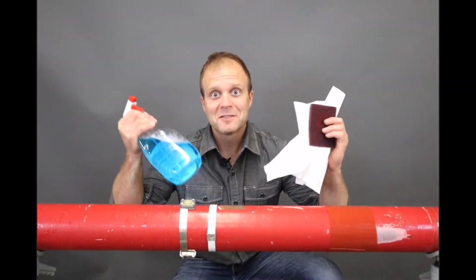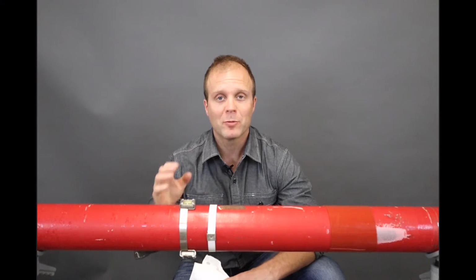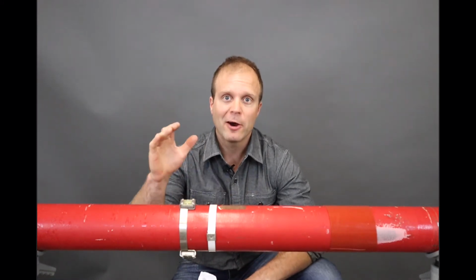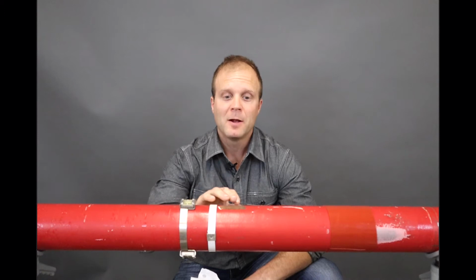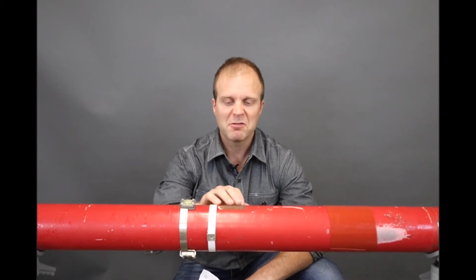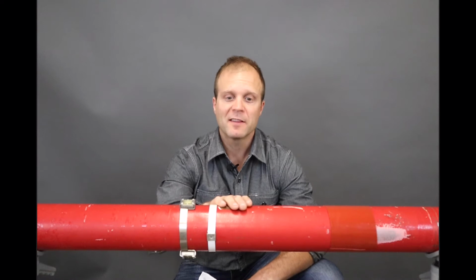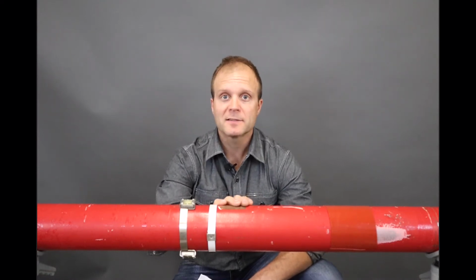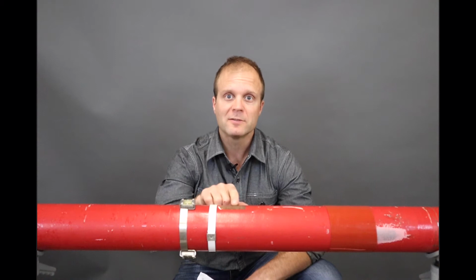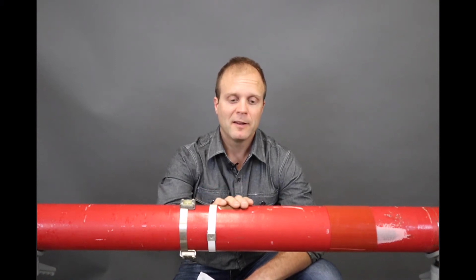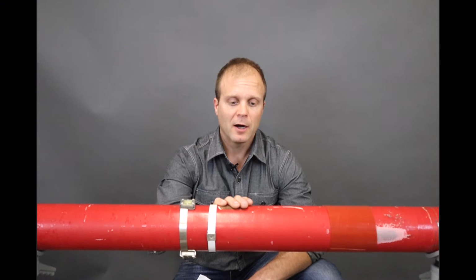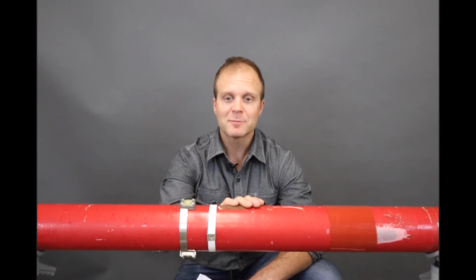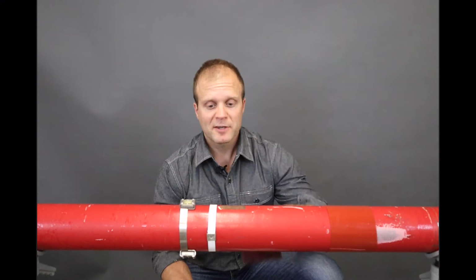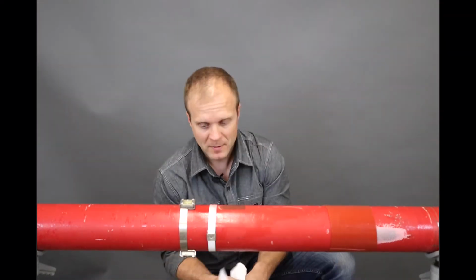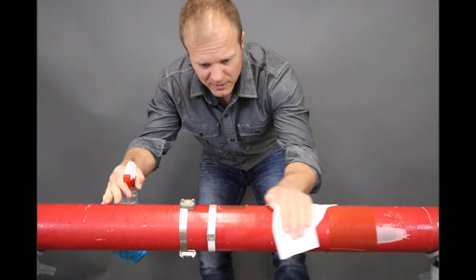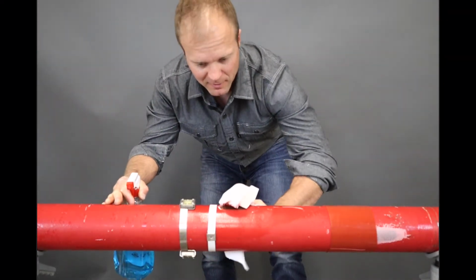Okay, step one is clean the pipe. This is important so that we make sure the sound is coming out of the flow meter and going straight into the pipe. If there's dirt, gravelly, muddy stuff on the outside of the pipe, flaky paint even, that can cause the sound to bounce around between the transducer of the flow meter and the pipe, and that can corrupt our measurement. So we don't have to go too crazy here, but let's just make it nice. I'm going to start off with some Scotch pad, some cleaner. Okay, a little more liquid, and wipe it down.